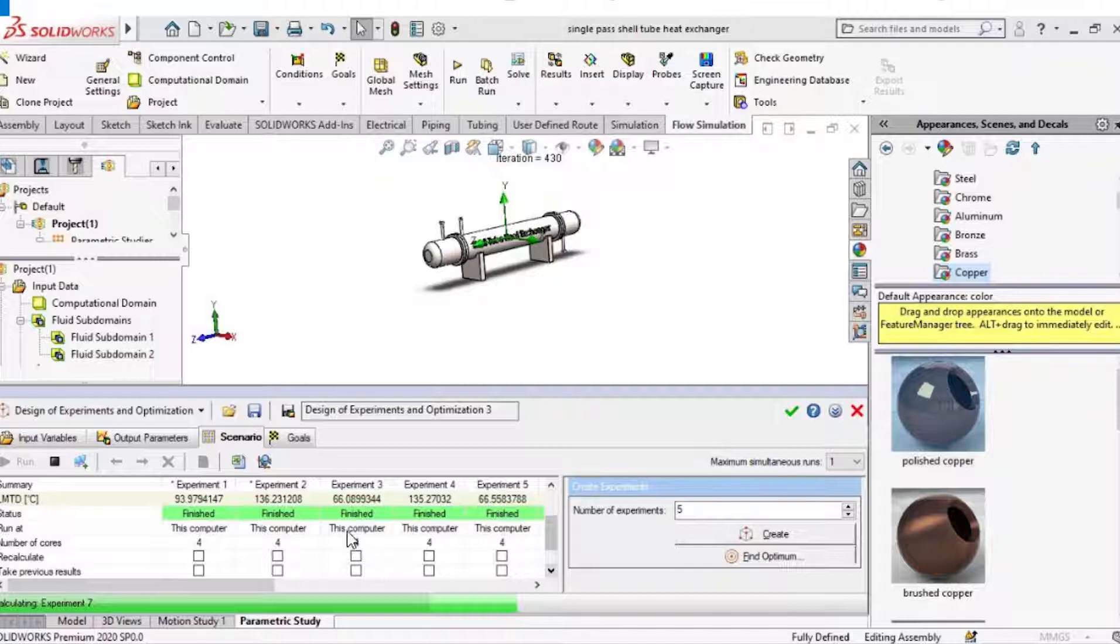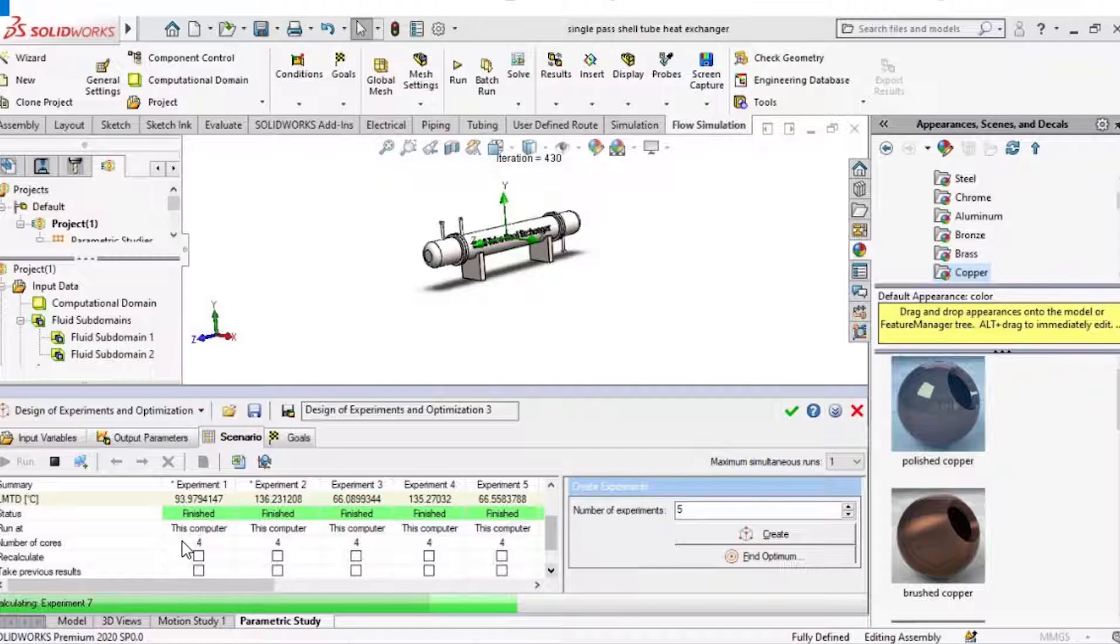These are the LMTD values. At different temperatures we got different values of LMTDs. We can see here the relation of temperature and LMTD is not linear. It is varying in a different way. From this data obtained from this parametric study we can go for optimization.